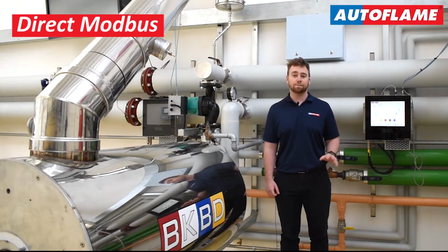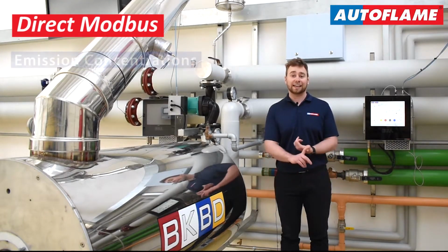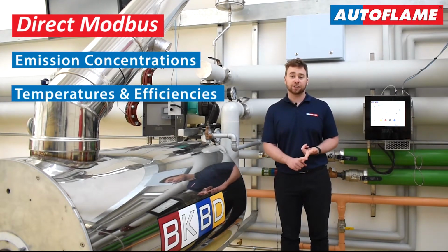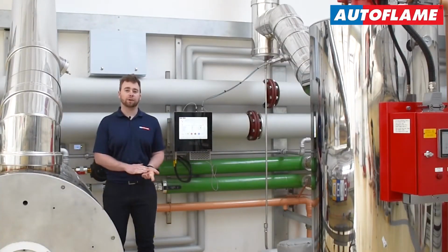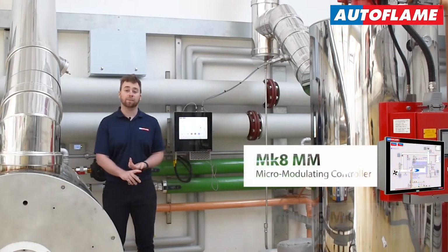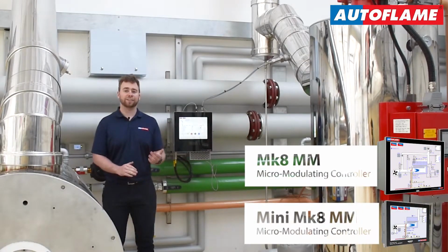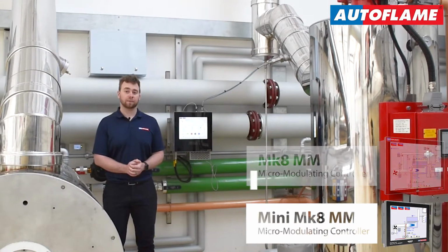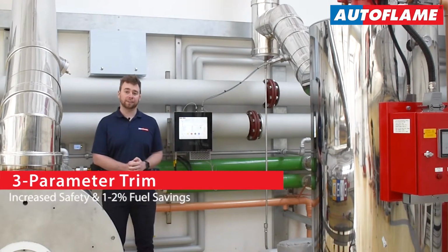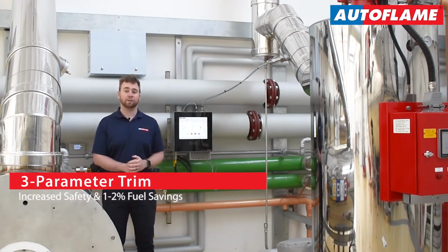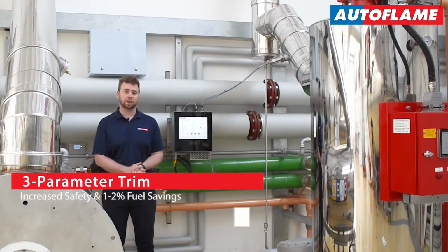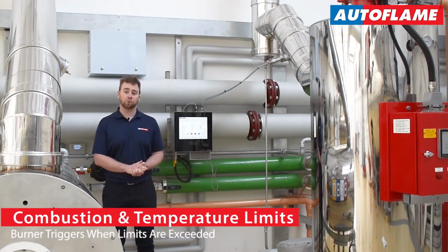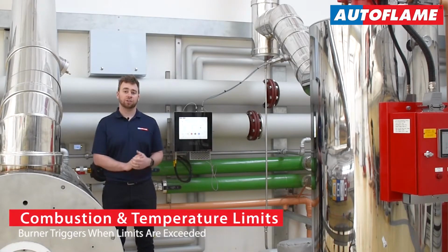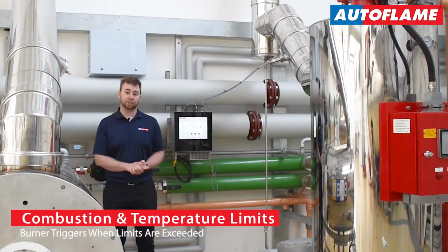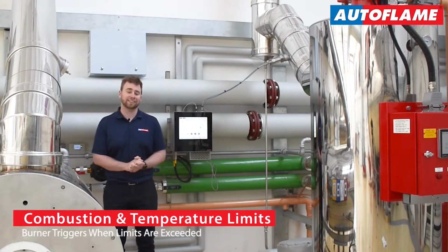This allows access to some more of the EGA's data, such as gas concentrations, temperatures and efficiencies, and EGA error codes. When coupled with a combustion controller, such as the Mk8 or the Mini Mk8, a number of additional features can be enabled. 3-parameter trim can be implemented, yielding increased safety and around 1 to 2% fuel savings. Combustion and temperature limits can also be set up, which ensures the burner locks out or a warning is generated once these limits have been exceeded.